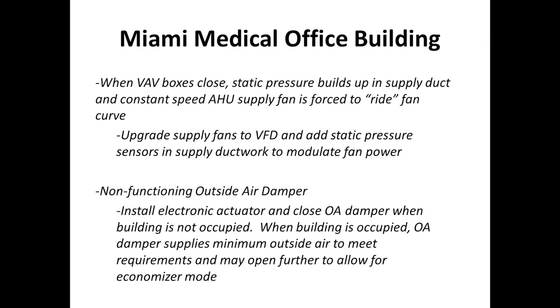Again, this building didn't have static pressure reset. When VAV boxes were closed, or stuck closed as was the case throughout this building, static pressure constantly built up in the supply duct, and the supply fans were working a lot harder than they needed to. We could add VFDs to these supply fans as a retrofit and control them based on static pressure reset, which allowed the fan motors to ramp down and save fan energy.